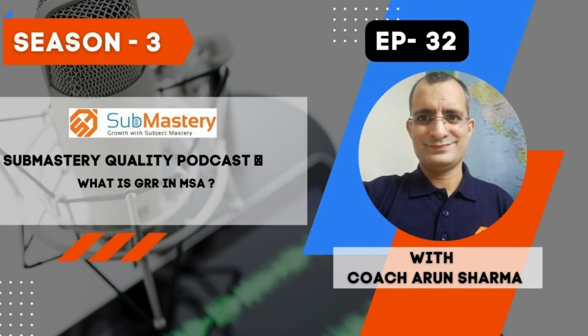Now let's try to understand the meaning of repeatability and reproducibility. Repeatability is the capability of an instrument to give the same readings or result when all other situations remain the same. So repeatability is basically your EV. What is EV? EV is not electric vehicles, okay? Here EV means equipment variation. So repeatability represents equipment variation. That's what we want to identify.